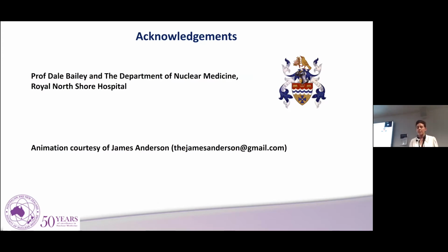Implementing the procedures that are involved to set this up does require a bit of work, and certainly you want to have some maintenance in terms of your quality control and so forth. So if you have a PET department where that sort of stuff is being done, I don't think it's going to differ very much to those demands. So in that respect, a physicist or a technologist who's familiar with SUV checks and so forth could probably handle that quite well.